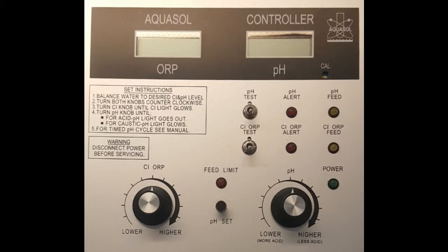Right. Now with the high alert, let's see. Yes, and I believe that's the same thing, 100 millivolts below or 100 millivolts high. Okay, so if we have it off, it's going to be a high alert, and that's going to be if the sanitizer residuals get too high, it'll go into alert, and that one clears on its own. Correct. So they don't have to unplug it to get that to reset.